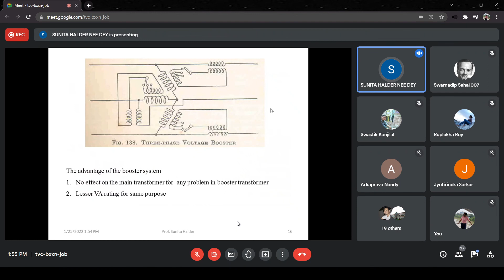Now what is the thing? Say for one booster onload tap changing transformer, the current is 100 ampere and the voltage level is 33 kV. Then what will be the rating? 33 kV into 100 ampere, that is the MVA. But for a booster transformer, say if you want to increase the voltage by 100 volt and the current is still 100 ampere, then your volt ampere rating will be only 100 volt into 100 ampere. So the rating will be very low, and the transformer cost will be lower. That is one advantage of the booster transformer.